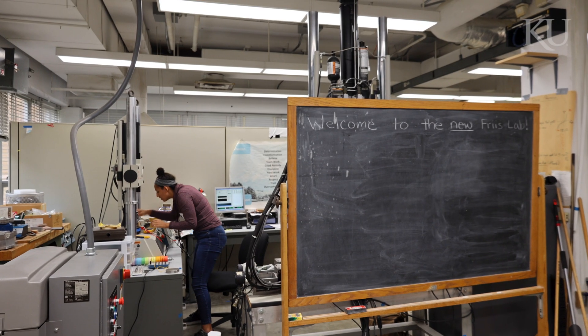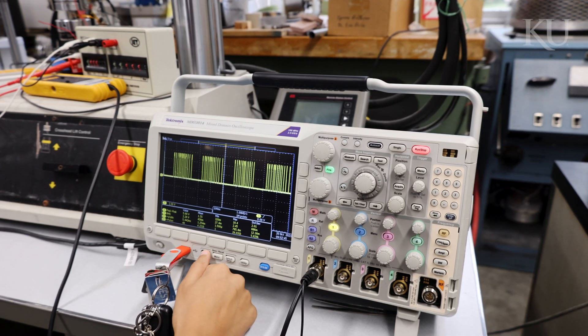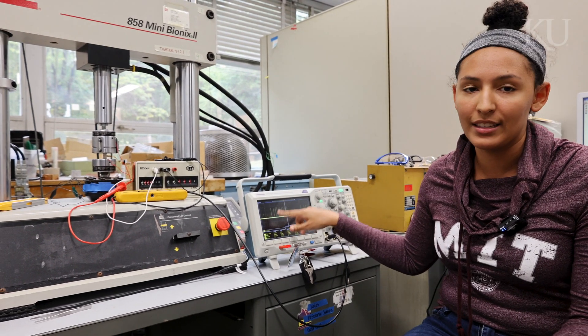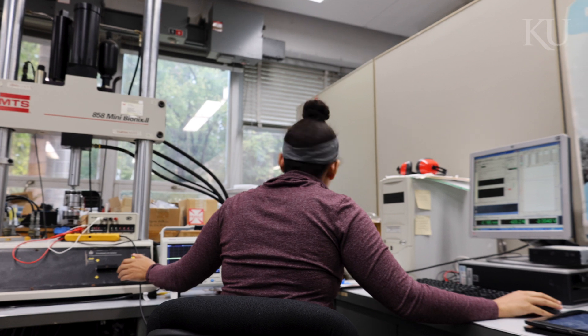This is one of our implants that we use a lot for experimental testing. What I'm doing right here is varying the resistance that the circuit is feeling and looking at what the electrical output — in this case voltage — is. That way when we're doing an experiment, we can look at what resistance our experiment uses and know exactly what the voltage output of our implant would be.